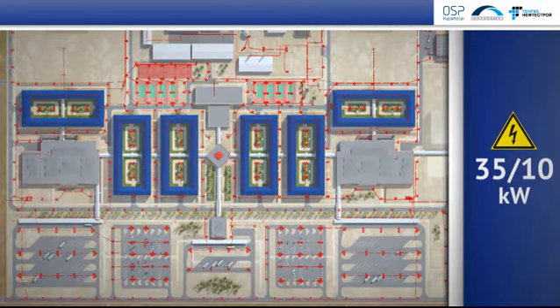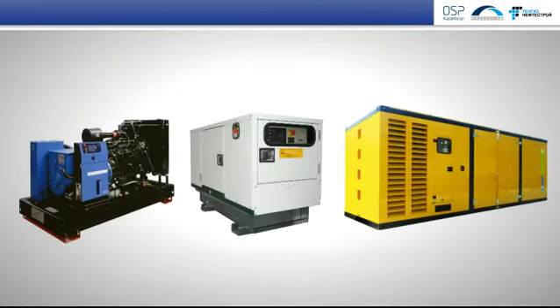These substations will each house a 10 kV incoming fused isolator, a 1000 kVA transformer, 400V switchgear, UPS units, and will each also house an appropriately sized diesel-fired emergency generator set.